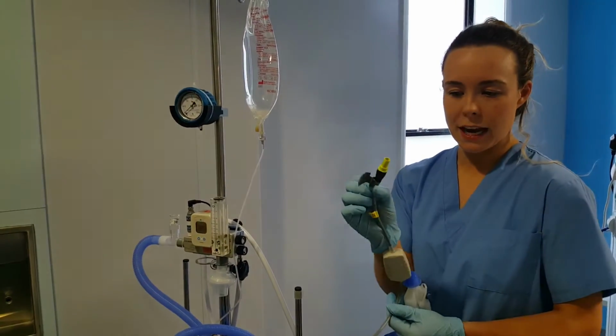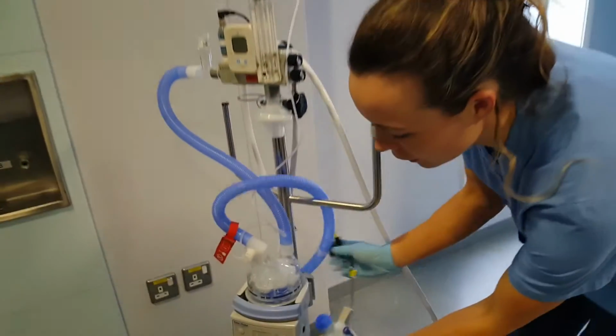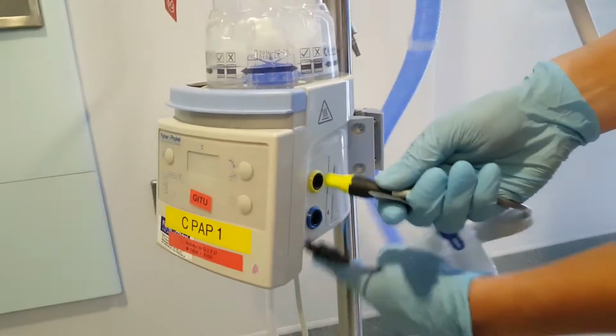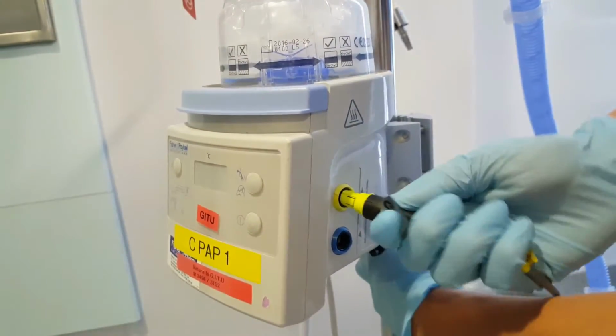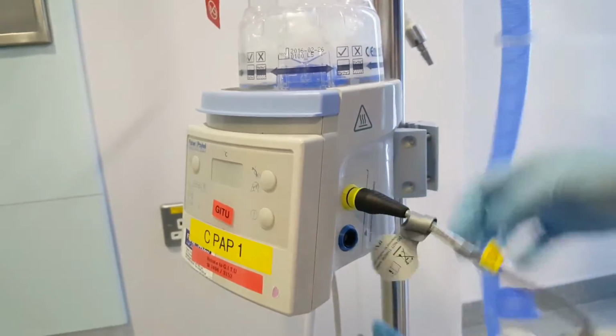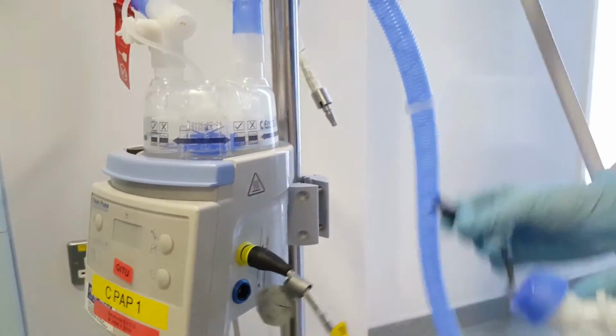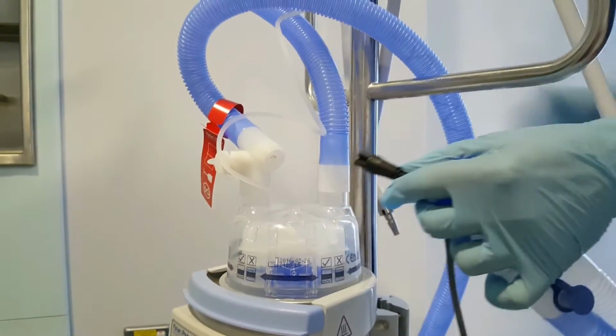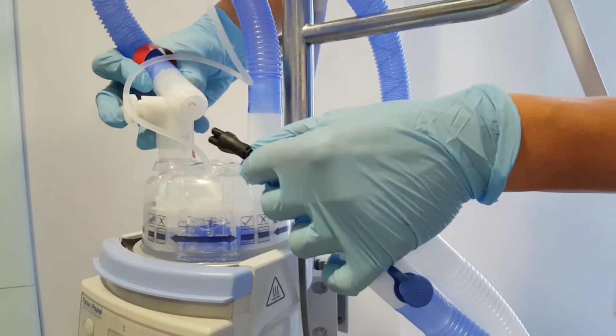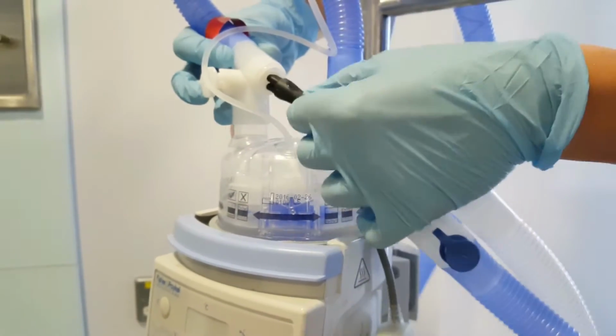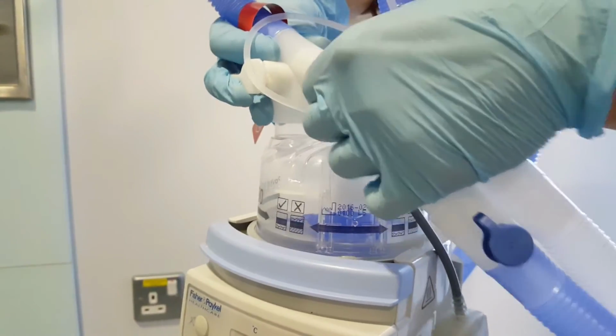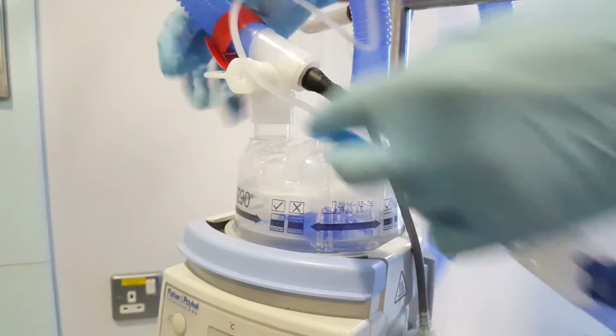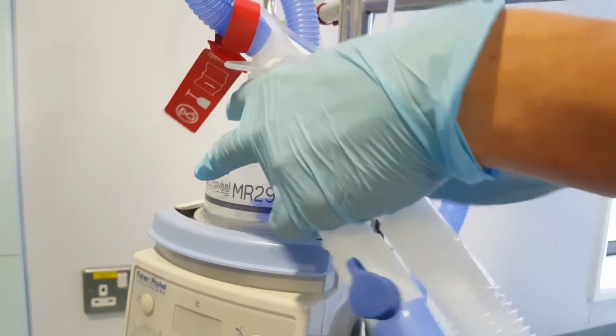The next step is to connect up our heating wires of the humidifier. So you connect yellow to yellow and blue to blue. So you just click it in. It can be a little bit fiddly. There we go. And the 3-prong connects into the back of one of your blue tubings, and it sits in just like this. And make sure you have it well secured in, or it will alarm. And that can go back like that.